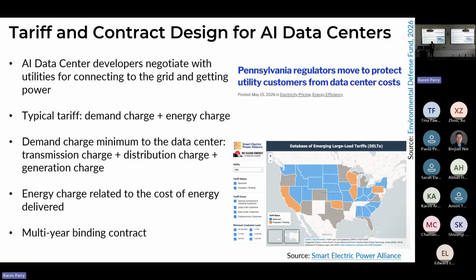Tariff design has become a major direction. AI data center operators directly negotiate with utilities through very opaque processes, you really don't know what's going on, it's all private. A typical tariff has a demand charge and an energy charge. You pay for how much demand you put on the grid, even if you don't consume anything, and you pay for how much energy you actually consume. The demand charge includes transmission, distribution, and generation charges, while the energy charge relates to actual energy consumption. And you want multi-year contracts.